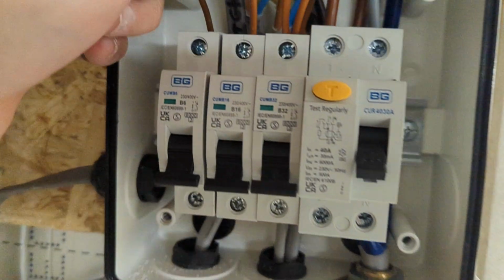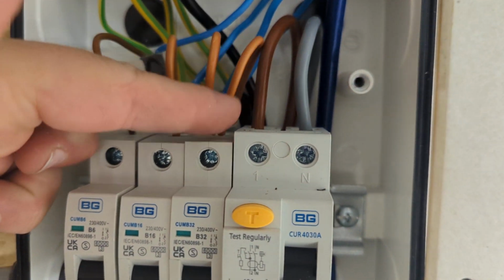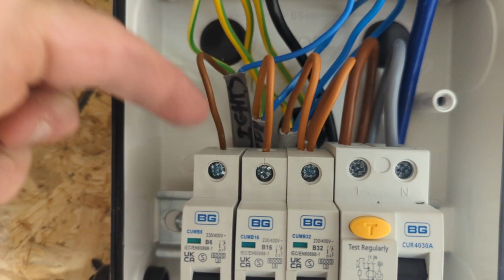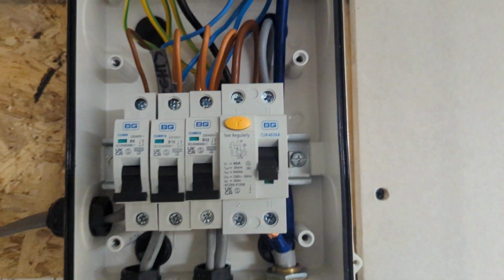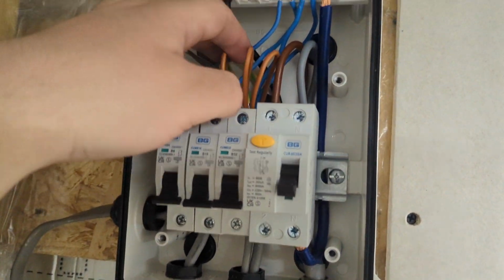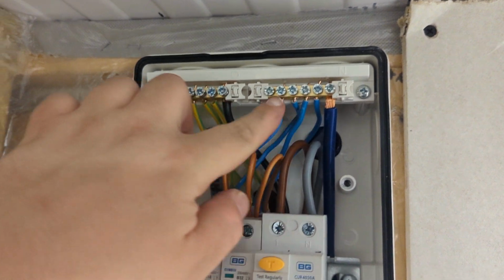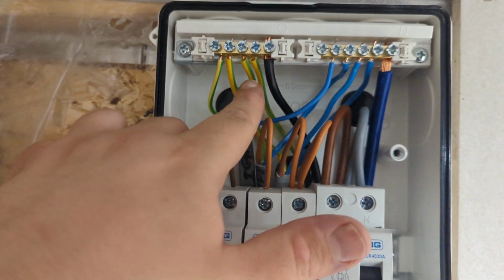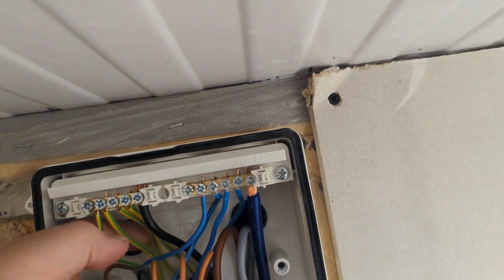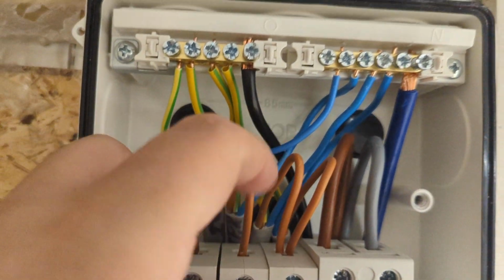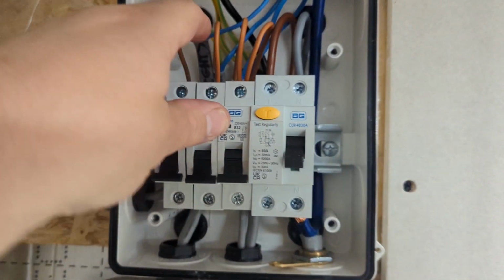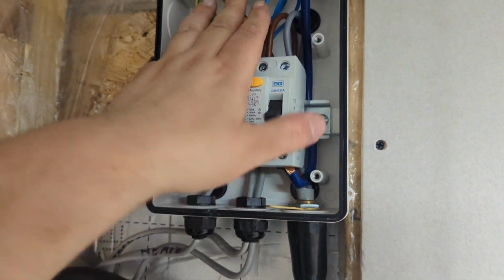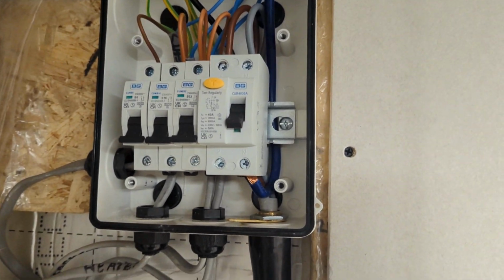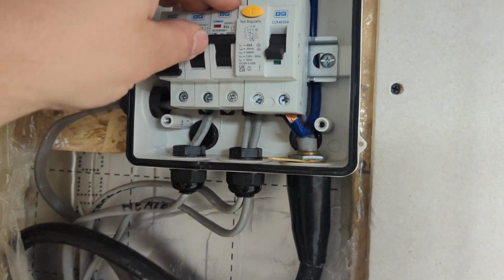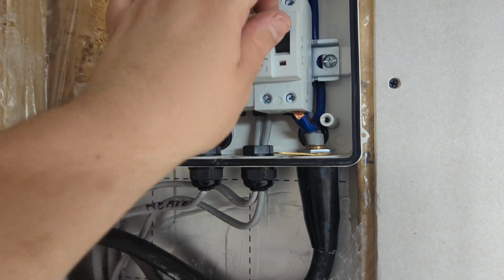You can see here the brown lives come over into the fuses, breakers, and then their neutrals go to their respective positions on the neutral bar, and their earths go to the same positions. It's a bit hard to see, but it is actually in order, and that makes debugging really easy - when something goes wrong and you're testing the circuits, it's very easy to isolate the correct ones and do it right.